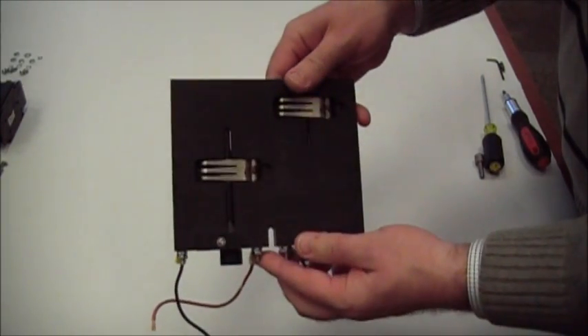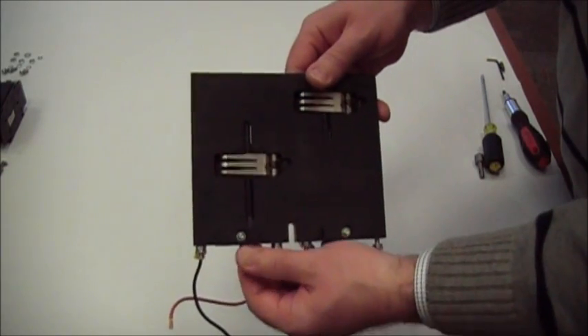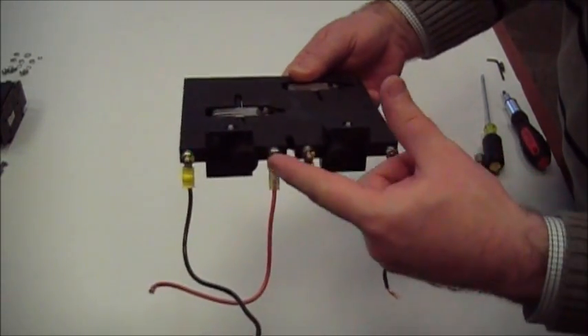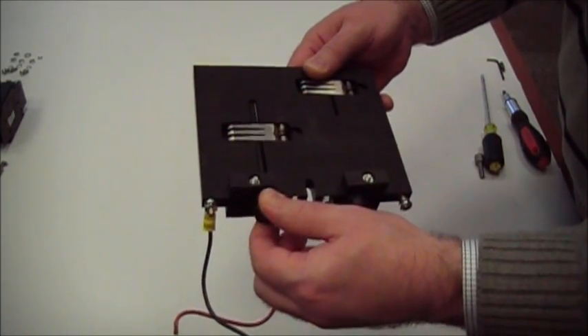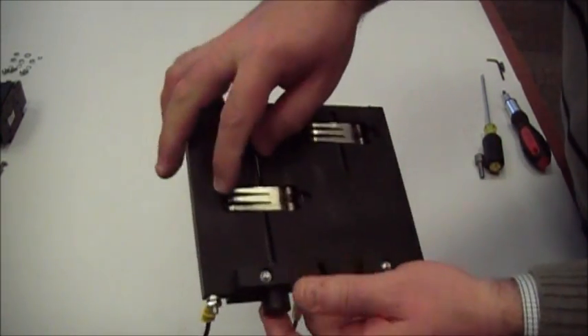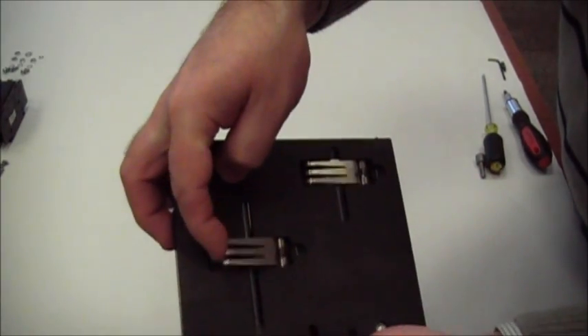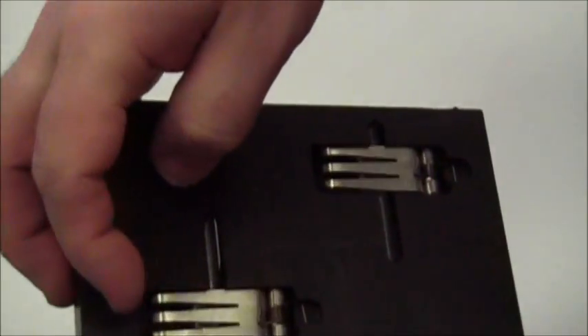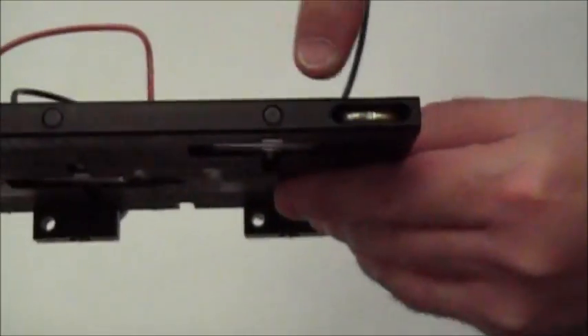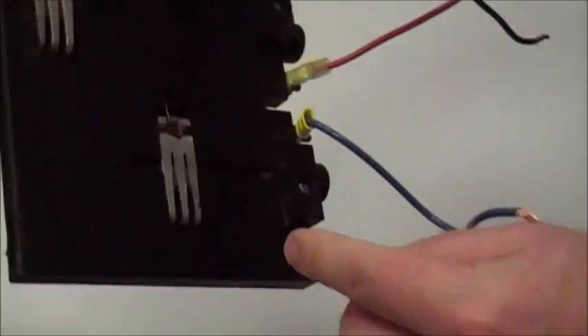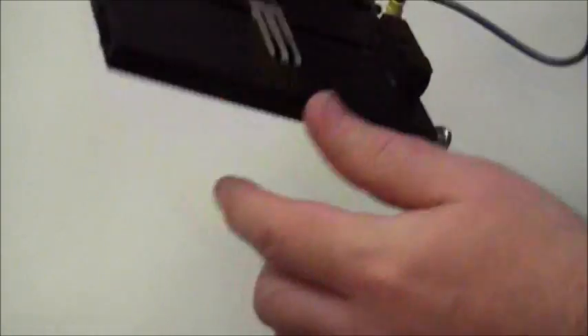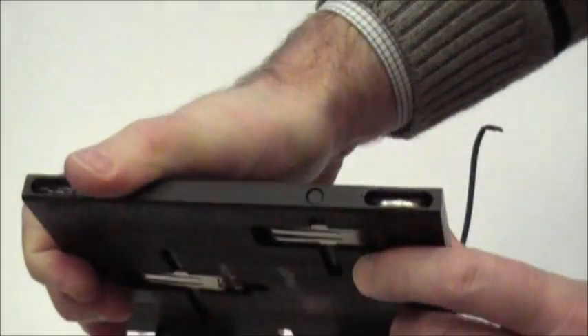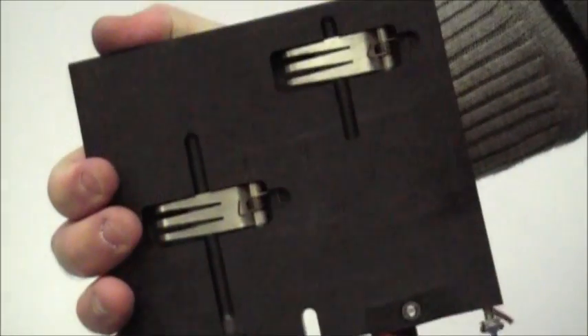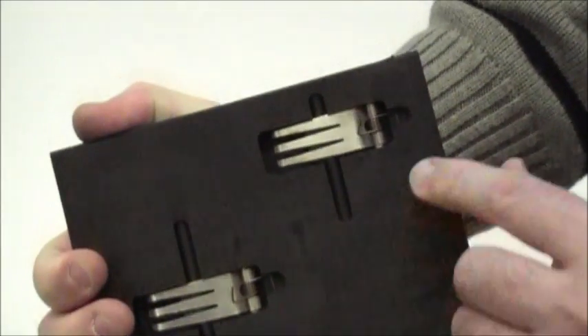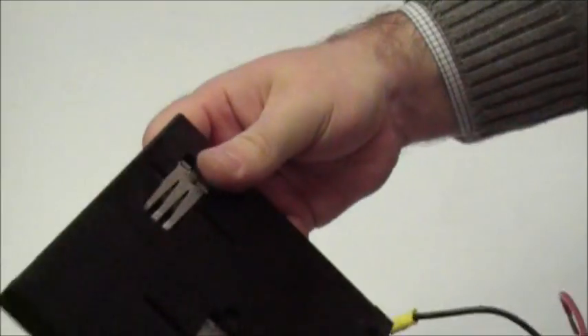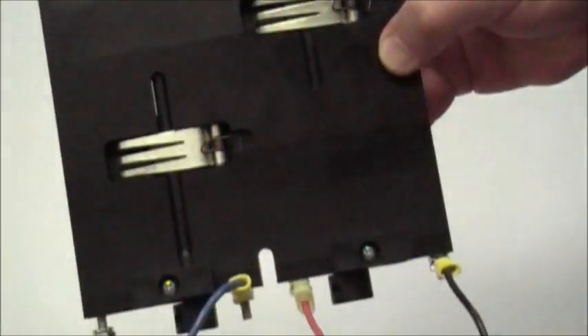Those connection points to the electrical connections to the fingers are a rotating assembly that goes around a fixed bar. So as you can see, the bar comes up and makes its way up through the paddle, comes down and makes a connection point there, and those fingers rotate around that fixed member with a spring that will return it back to its normal position when the paddle wants to be removed from the busway itself.